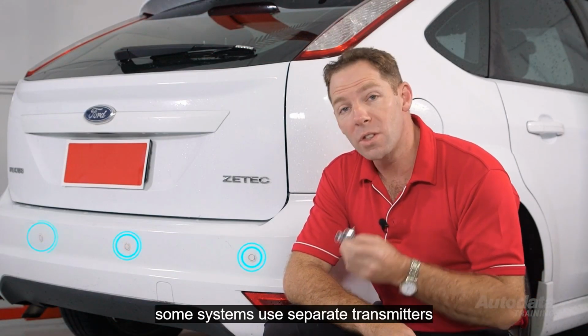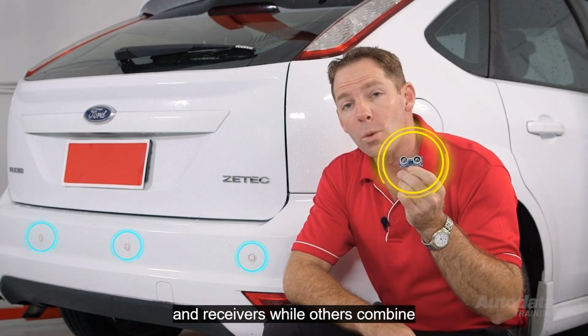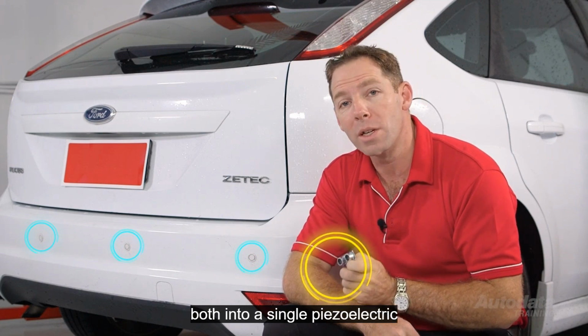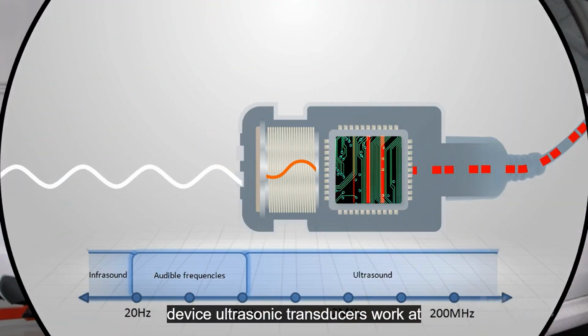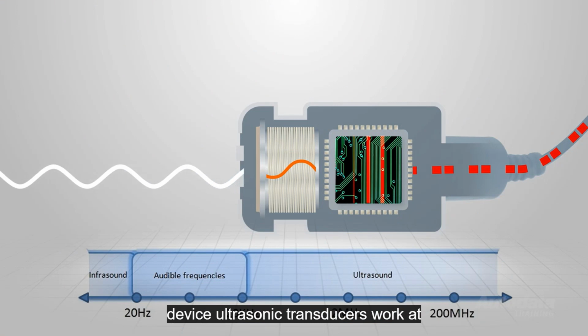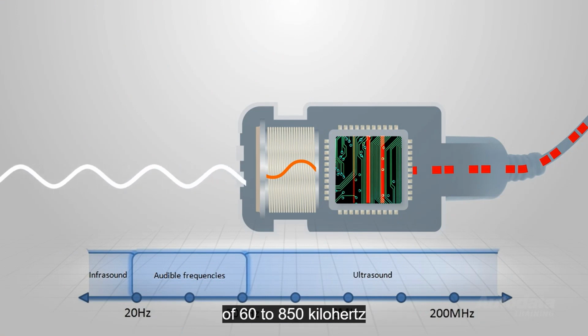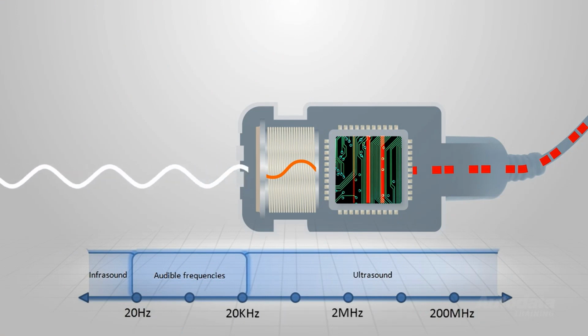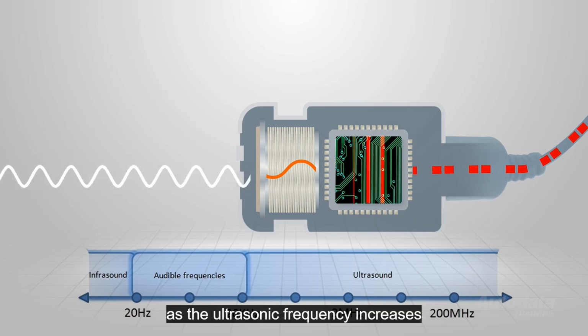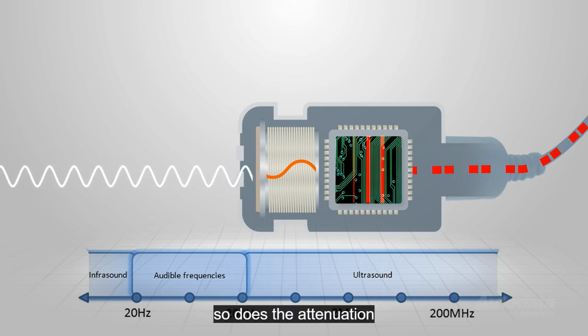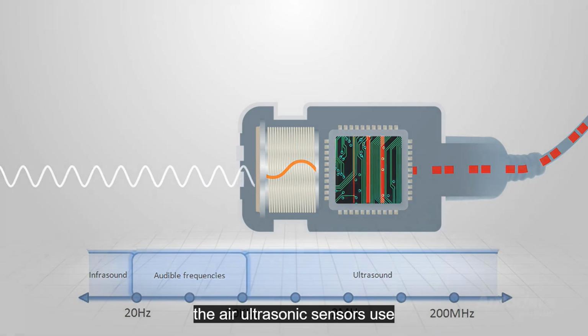Some systems use separate transmitters and receivers, while others combine both into a single piezoelectric device. Ultrasonic transducers work at different frequencies in the range of 60 to 850 kHz. As the ultrasonic frequency increases, so does the attenuation of the sound waves in the air.